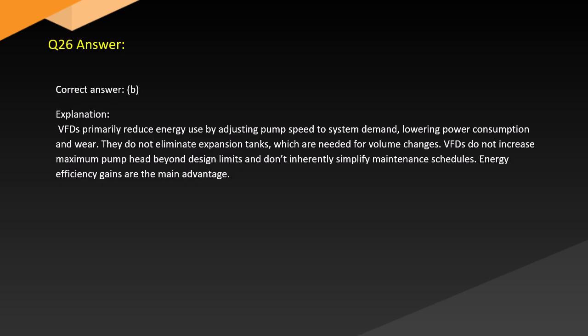Answer. Correct answer, B. Explanation. VFDs primarily reduce energy use by adjusting pump speed to system demand, lowering power consumption, and they do not eliminate expansion tanks, which are needed for volume change. VFDs do not increase maximum pump head beyond design limits and don't inherently simplify maintenance schedules. Energy efficiency gains are the main advantage.